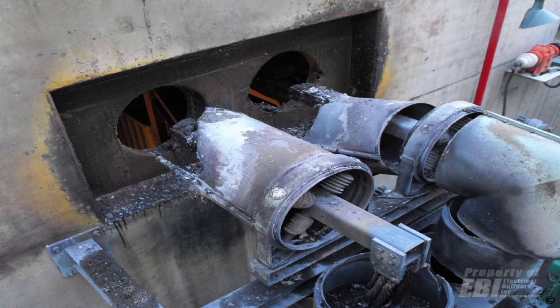This is what happened at this plant. You had two phases that came through a wall, and where they couldn't get in and clean the seal-off bushings where they went through the wall, the plant personnel actually put fire-stop foam around that and sealed that part of it up. That caused tracking on the inside, and then you have the damage here. On this failure, it actually went on for 7 seconds before it shut the generator down.